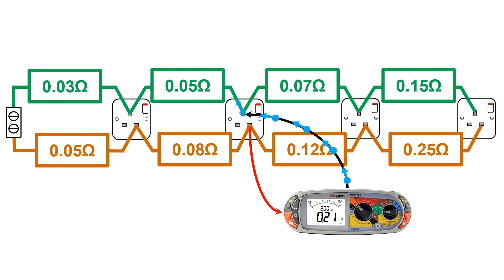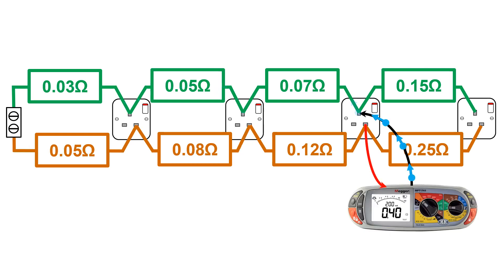With test method one, as we move through the circuit, the loop from the connector block gets bigger and as such, the resistance increases. Each point, tested downstream of the supply, increases the distance the electrons have to flow and the resistance increases proportional to the length.